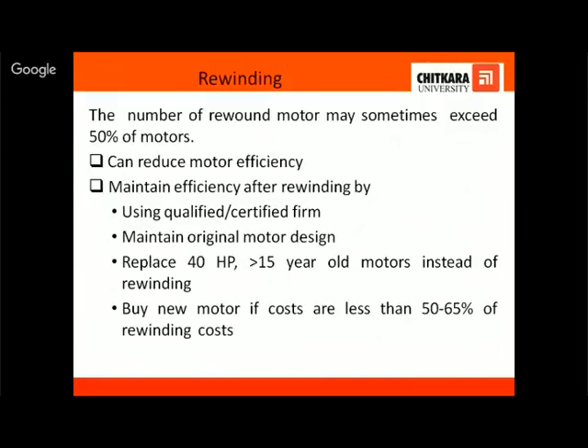Get the motor rewound only from a certified firm and see that the motor maintains the original motor design. And if the motor is 40 HP or greater and more than 15 years old, then instead of rewinding, buy the new motor. Replace it with an energy efficient motor, and buy the new motor if the cost is less than 50 to 65% of the rewinding cost.